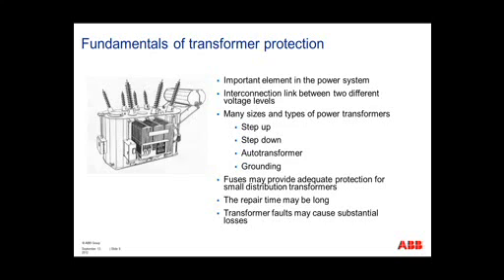There are many types and sizes of transformers. You have a step-up. Step-up transformers are typically used with generators, if you want to step up, say, 13.8 kV to 161 kV. You have a step-down transformer. You can see these step-down transformers typically connected to distribution networks. You have autotransformers. Autotransformers are typically Wye-Wye transformers connecting two voltage levels in the transmission system together. Say if you needed to connect a 500 kV loop to a 161 kV loop, you could do this using an autotransformer.